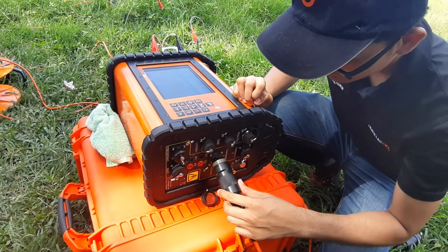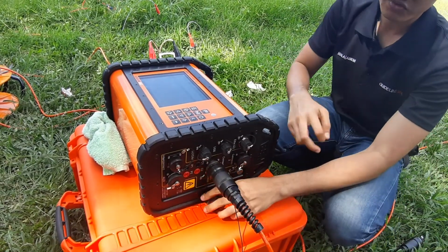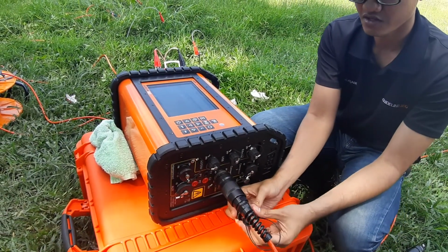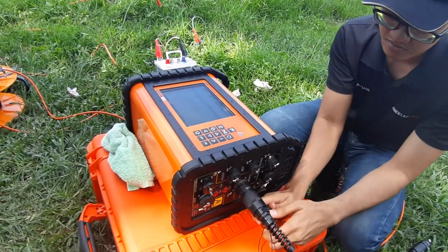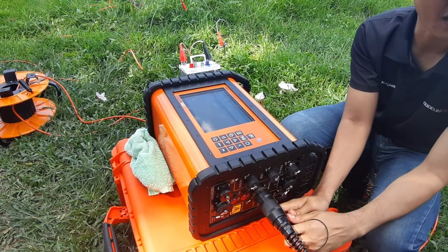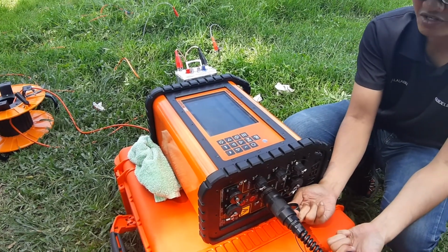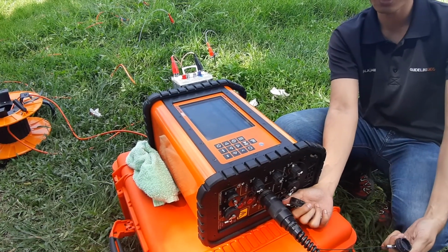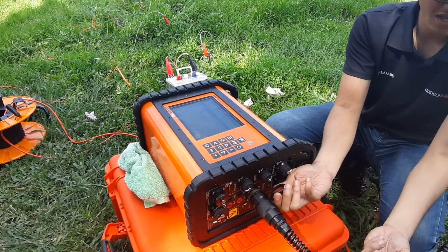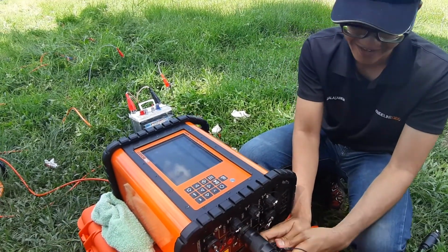Just see the groove. And then always keep this cap tight, because this is really important when you have water splashes and everything. That's why we claim IP66 when you tighten everything. If this is open, we don't claim IP66. Let's say the customer complains we have a broken instrument. How do you do that? This cap is open and everything. So no warranty in that part.